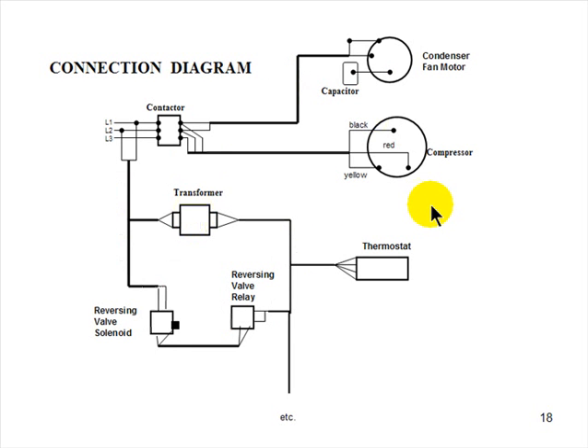This is a connection or hookup diagram, they call it sometimes, that the installers want to have so they know what size cable to bring. From here to the compressor, I need a 3-wire. Then I need a 4-wire up here, and out of the transformer, I need 5 wires going to the thermostat, that kind of thing. Here's the reversing valve relay again, but you can't tell from looking at this whether it's energized in the heating or cooling mode. The schematic tells you that. So those are the 3 kinds of diagrams: ladder schematic, pictorial, and connection diagram. We use the schematic diagram primarily.